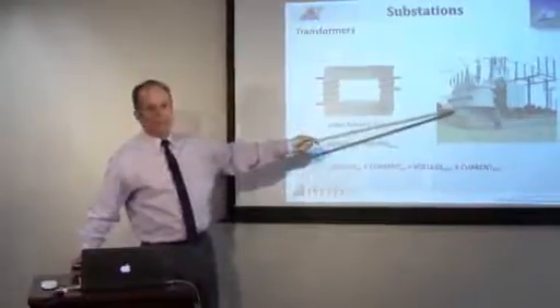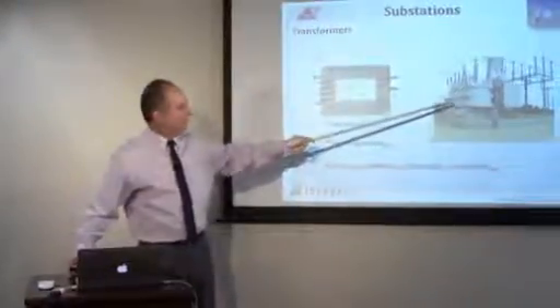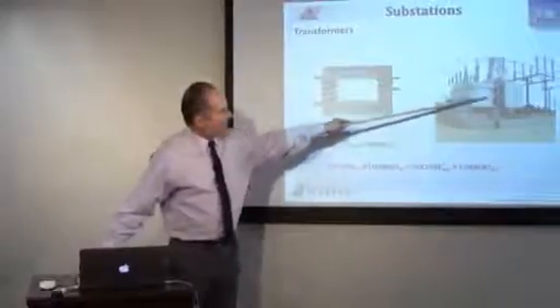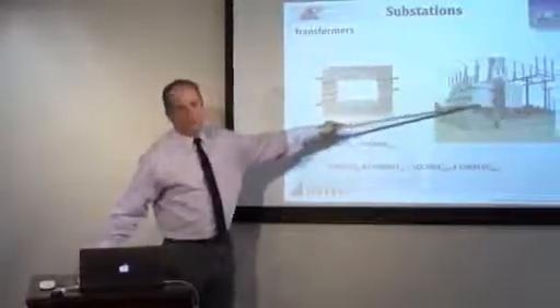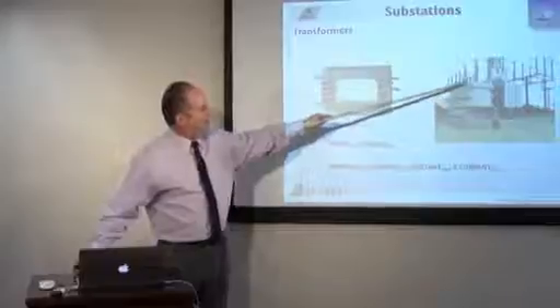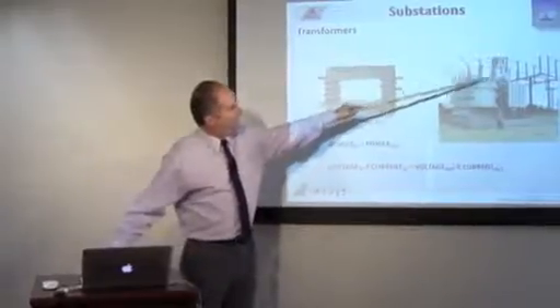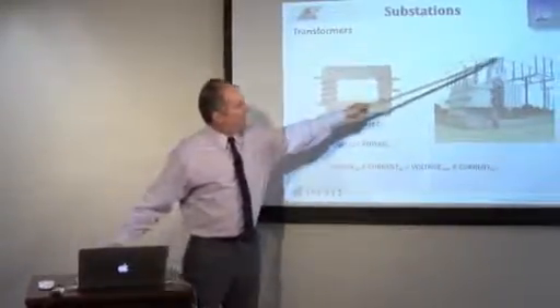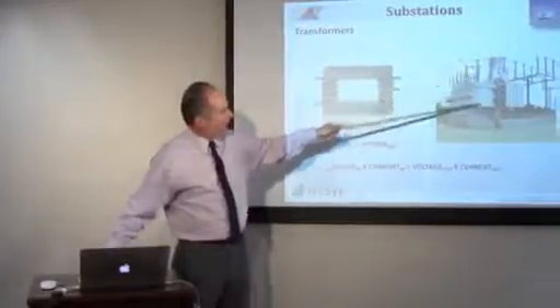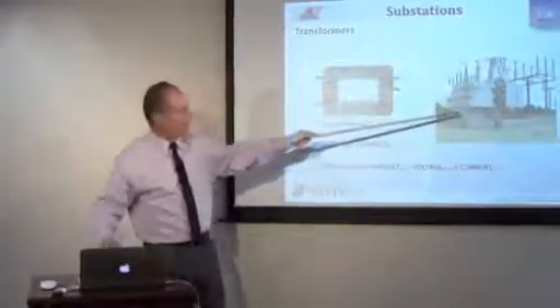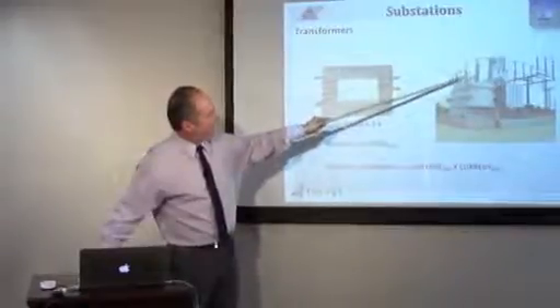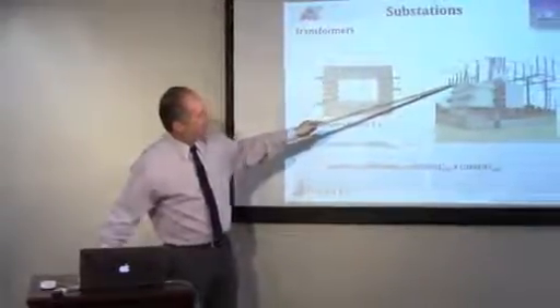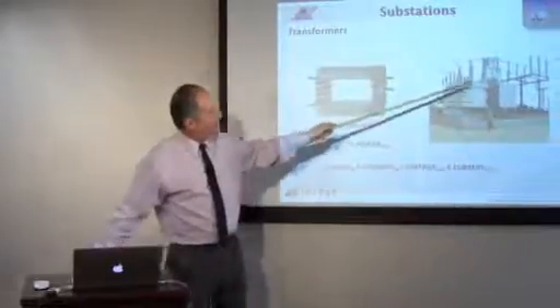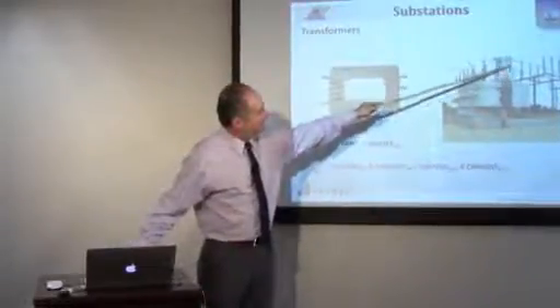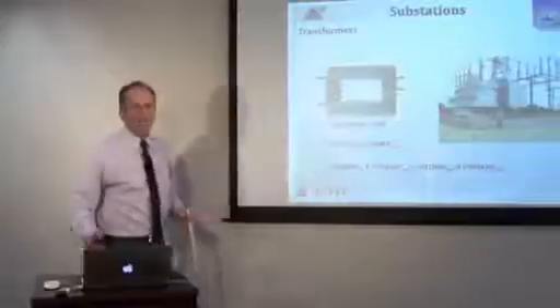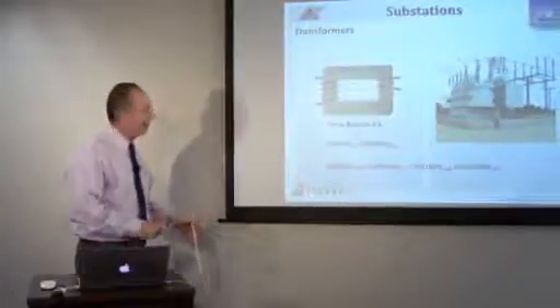Now, when you look at this transformer, there are a few things to note. This is the transformer itself, where the coils and the windings are inside. Up above are the bushings that connect the high voltage wires to the coils inside. We'll talk about bushings in a second. Then there are the low voltage bushings, and the lightning arresters. You can't see it too well here, but there are lightning arresters on the high voltage side and on the low voltage side.